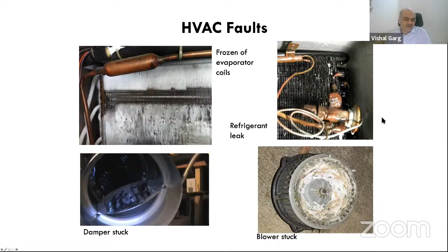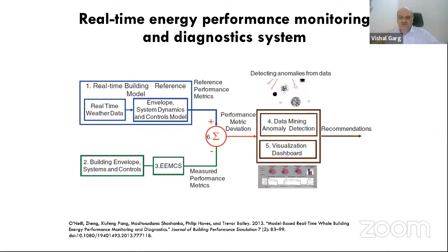A lot of interesting methods are there. I'm just giving you an idea that such things are going to help us operate our buildings efficiently, reduce faults, and save energy, even the small amount that gets wasted because of some small fault in the devices. So one of the ways is that we can do real-time simulation and find out the expected performance of the building, the expected parameters, and compare it with the actual parameters. If there is a mismatch, we can find out that there is a problem.